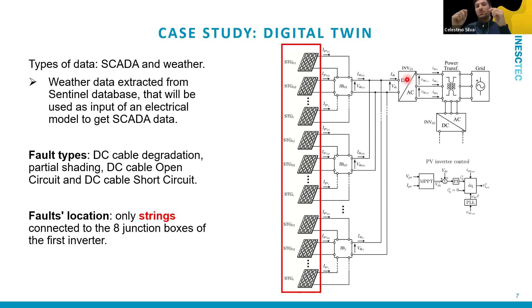So degradation refers to a gradual increase in the series resistance in the cable of a string over time. Partial shading results in a reduction of irradiance affecting a string. Open circuit occurs when there's an open circuit in the string cable. And the short circuit refers to a small resistance path between the positive and negative terminals of a string.